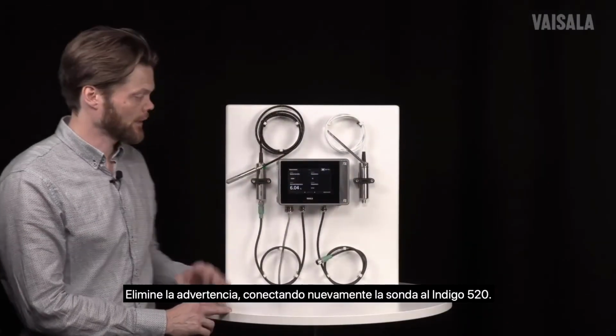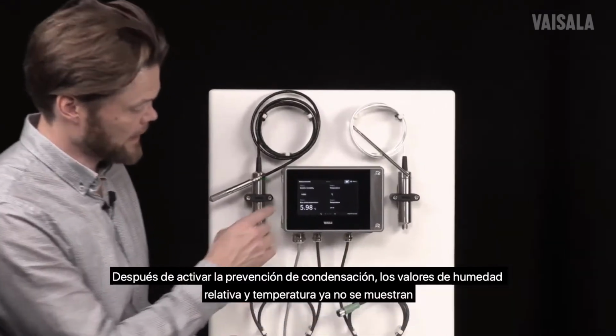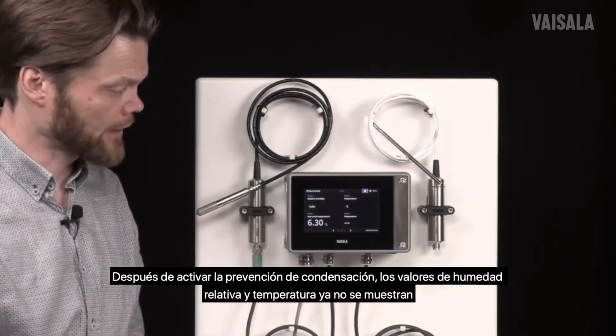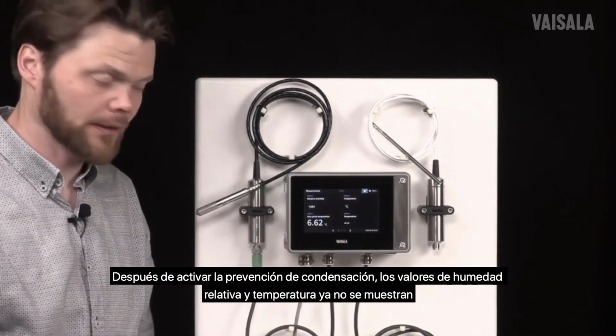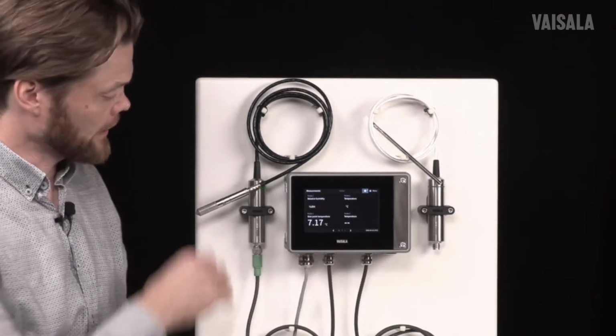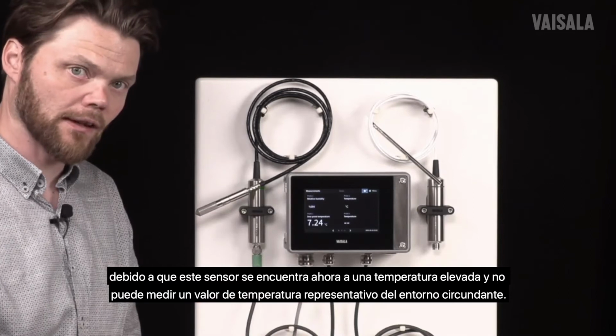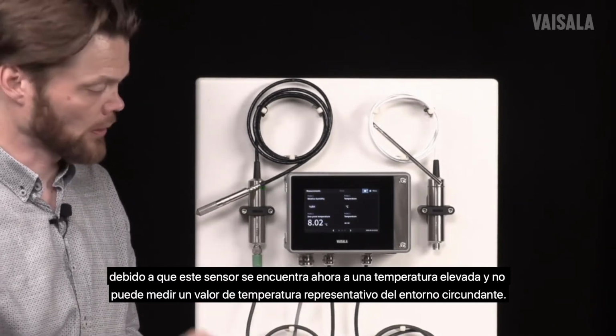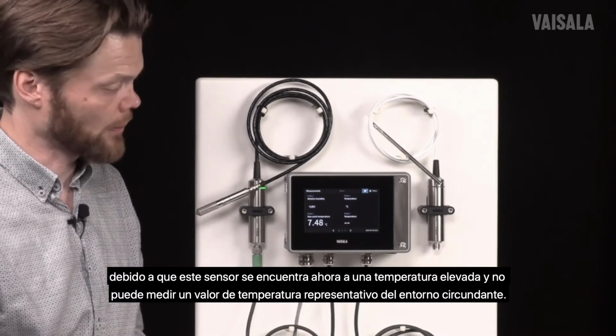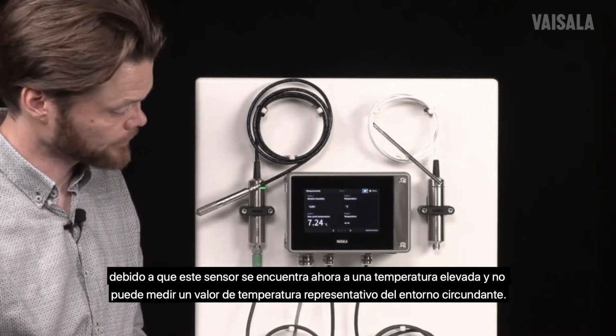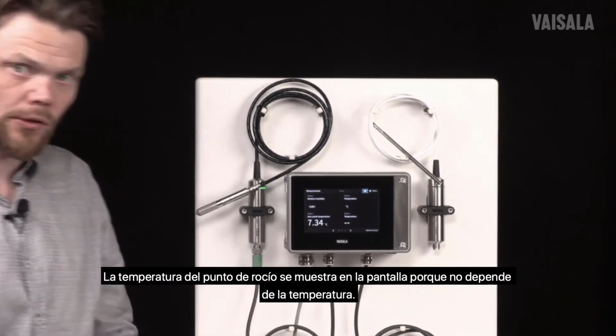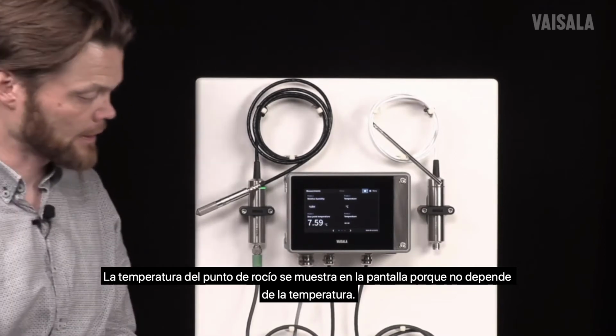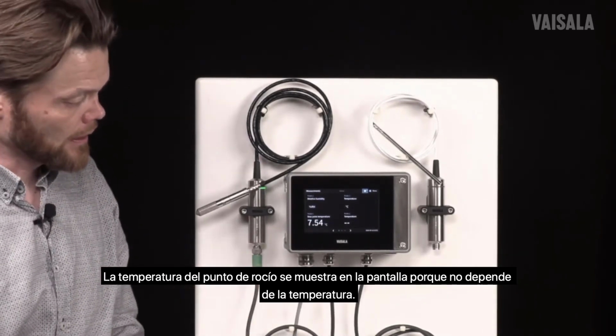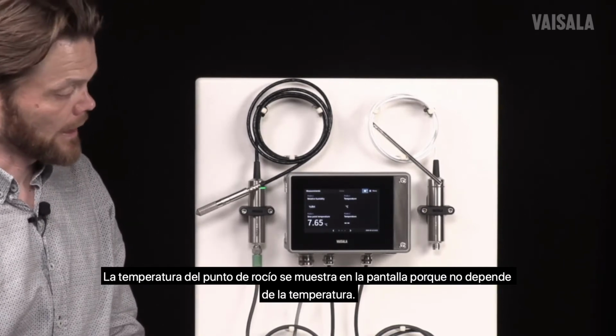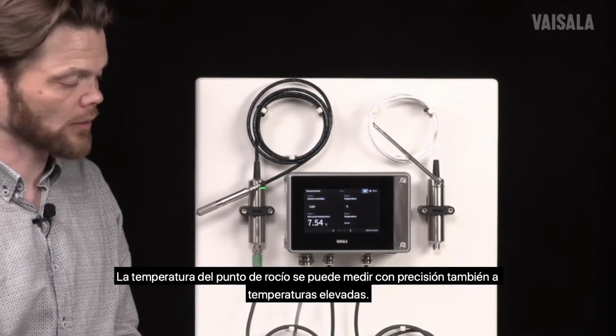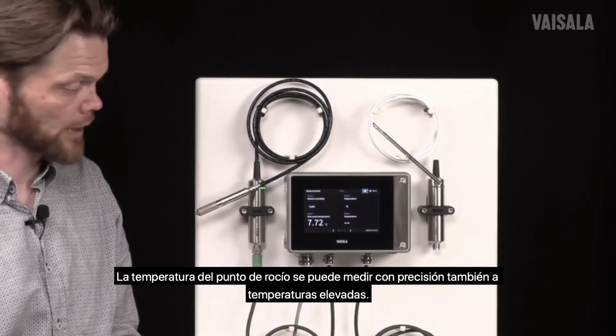Now that I have activated condensation prevention, we can see that we are no longer seeing the relative humidity value or temperature value, and the reason is that this sensor is now in elevated temperature, and it's no longer able to measure a representative temperature value from this surrounding environment. However, dew point temperature is still there in the display, and this is because dew point temperature is not temperature dependent, meaning that even if it's in elevated temperature, it can still be measured accurately.